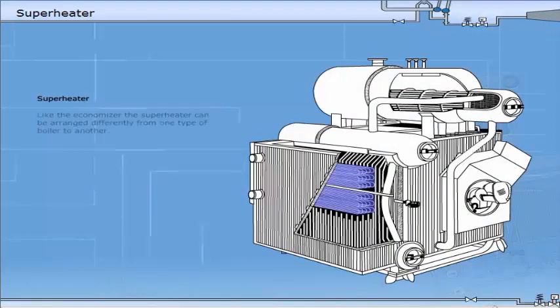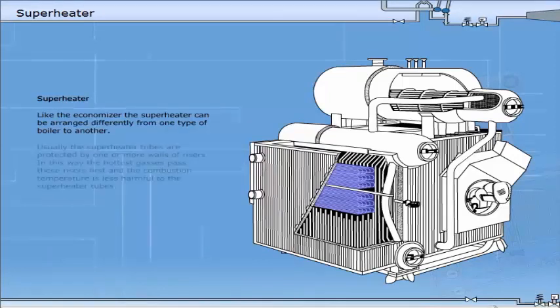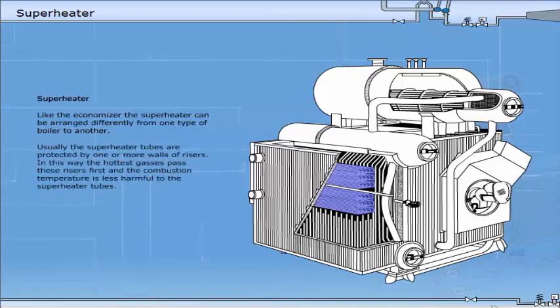Like the economiser, the superheater can be arranged differently from one type of boiler to another. Usually the superheater tubes are protected by one or more walls of risers. In this way the hottest gases pass these risers first and the combustion temperature is less harmful to the superheater tubes. The steam outlet temperature from the superheater can be well above 500 degrees centigrade.